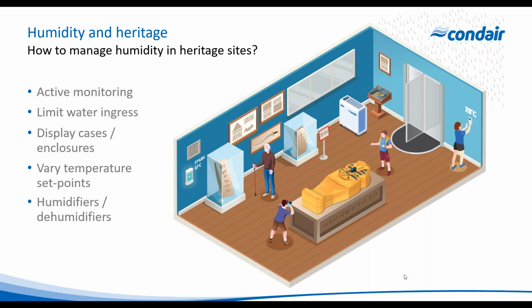And of course, humidifiers or dehumidifiers to increase humidity or reduce relative humidity. Now, if we've got in-room dehumidifiers and humidifiers, we need to make sure that there is a dead band between the set points of both, because each will have a control tolerance of maybe plus or minus 5%. So we need to allow that variance in the space and have a dead band between the two to make sure that they're not fighting each other.